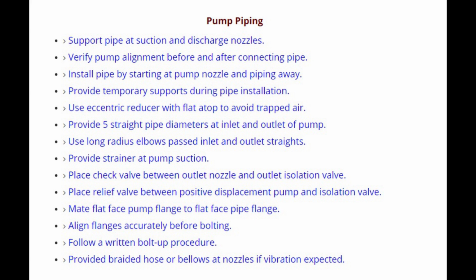Number 8. Provide strainer at pump suction. Number 9. Place check valve between outlet nozzle and outlet isolation valve. Number 10. Place relief valve between positive displacement pump and isolation valve.